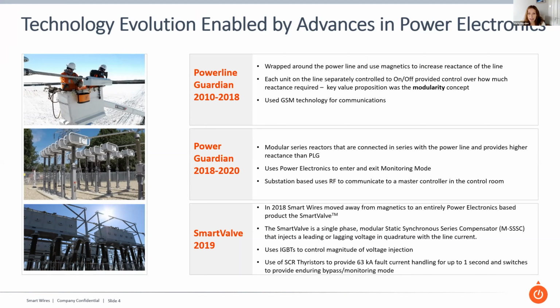So the SSSC technology, unlike our predecessors where we were using magnetics to physically change the reactance of the lines, what we do with SSSC technology is we create a voltage waveform and we inject it into the line in series with the line and 90 degrees out of phase with the line current. And that has the effect of increasing or decreasing the impedance. The beauty about using power electronics is you can either go lagging or leading the line current by 90 degrees, and that allows you to move from an inductive mode to a capacitive mode very seamlessly. So you can either push power off or pull power onto that line, depending on what's happening on your grid at that time.